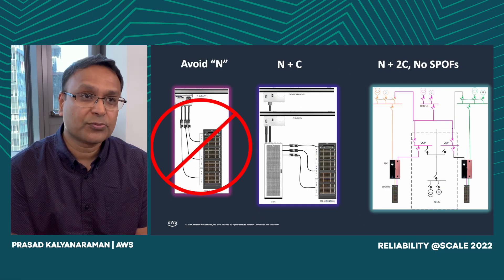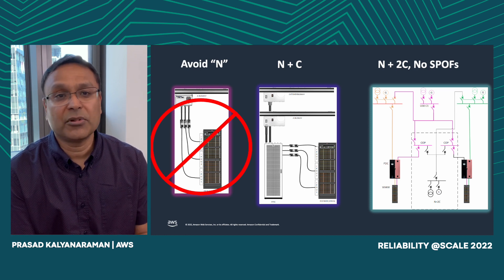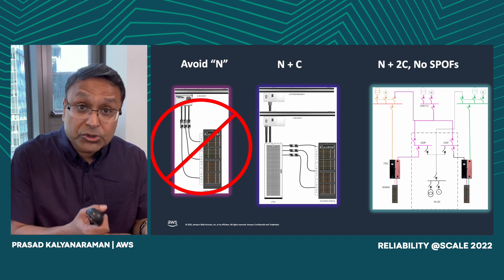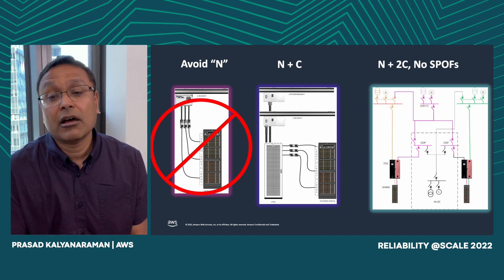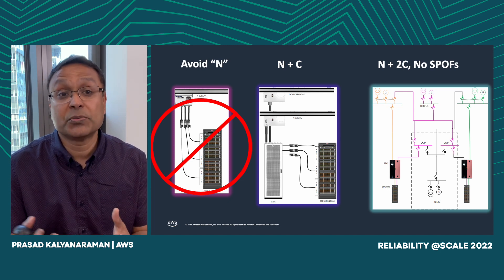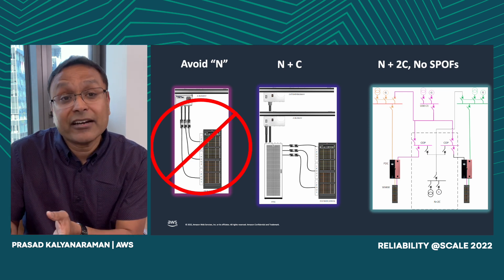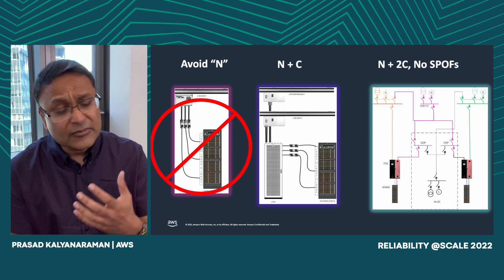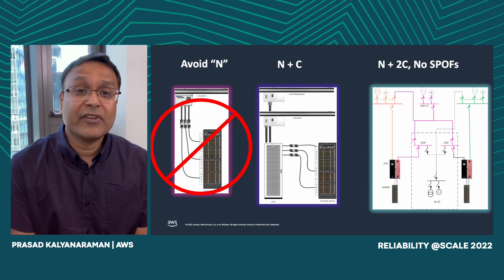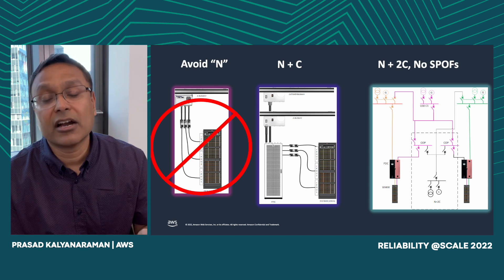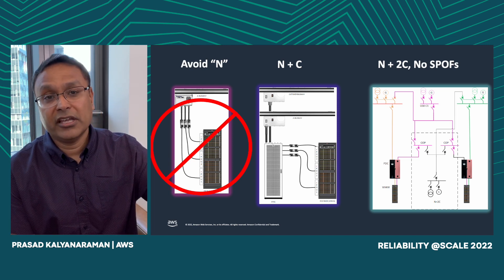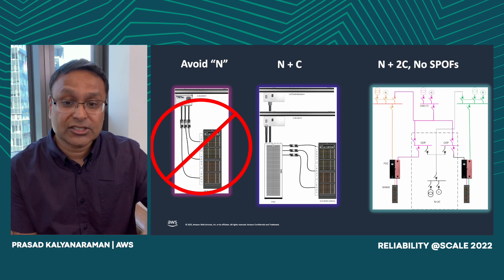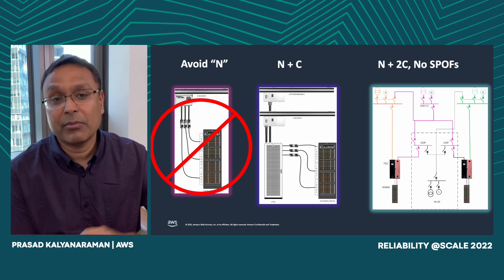We realized we actually need to design with N plus 2C. The reason is that when you do maintenance on a particular lineup — like breaker maintenance — you become vulnerable because you've reduced redundancy. So our latest designs have N plus 2C, meaning two catchers: two lineups independently available to take load if there's a problem on a primary. We also ensured there's never a single point of failure across the entire electrical infrastructure, from the utility feed to the changeover panels, PDCs, and ATSs — which we moved to the racks themselves, including battery backup units on the racks.